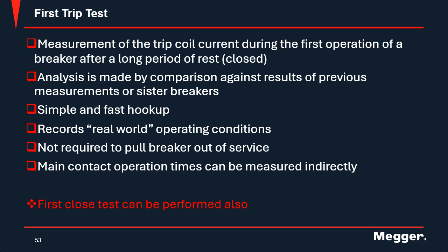and that's the one that's most important, because that's the one that's going to happen if there is a fault on your line and that breaker has to open. If it's outside of that tolerance of speed, how fast it needs to operate, you may have a catastrophic failure inside your circuit breaker, and normal testing does not catch that, just the First Trip test does.